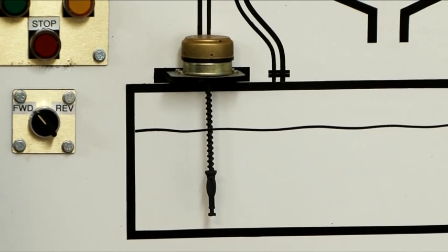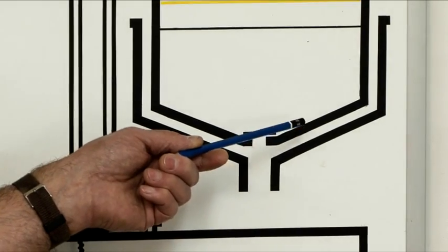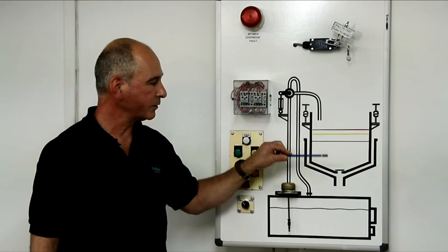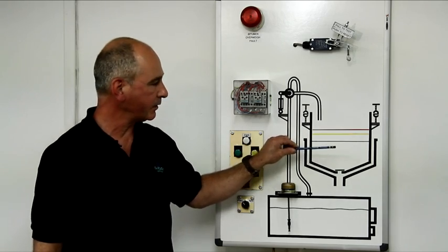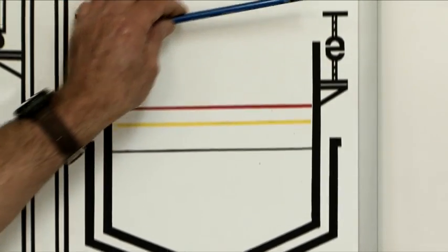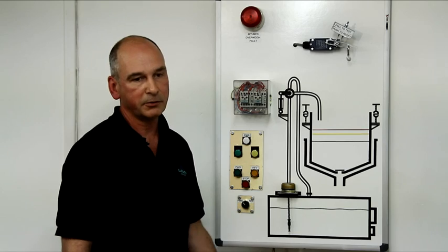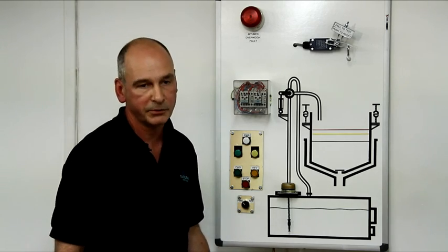In some cases if there is a fault with the load cells or there is debris or contamination between the outer and inner weigh kettle, then the control system will be fooled into thinking it's got the wrong amount of bitumen in the weigh kettle. The bitumen will continue to rise and overflow into the plant, running down with the potential to cause serious harm or potential fatality.